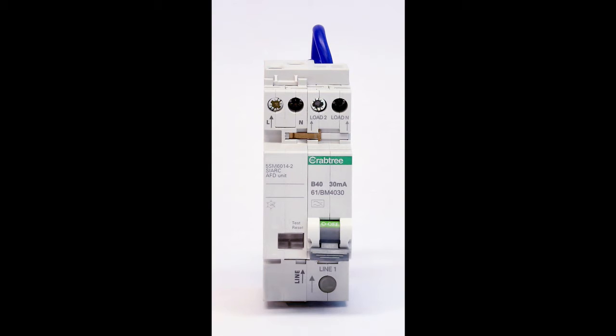Only use manufacturer-approved parts. Another new regulation, 536.4.203, refers to devices and components that are used in low voltage assemblies, such as consumer units, must only be those that have been declared suitable for that purpose by the manufacturer of the assembly. Or, put another way, only use manufacturer approved parts. Don't mix brands of devices or control items. Using unapproved parts will invalidate manufacturer guarantees and may result in an unsafe installation.